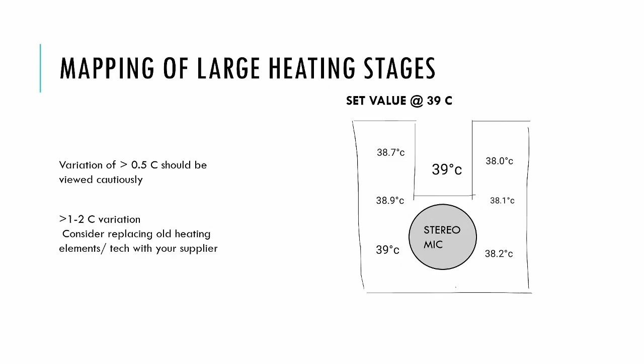When you're calibrating large heating stages like the laminar flow heating, it's quite a large area. That's what I have shown in the picture. You have the stereo zoom microscope, and the right hand side and the left hand side. Ideally you should have three separate temperature sensors: for the stereo zoom microscope, that is the heating plate, and the right hand side and the left hand side. Some manufacturers just have one sensor, and the problem is there is a large temperature variation happening across the table. If the variation is around 0.5, it is okay, it is normal. If it is more than 1 or 2 degrees, then there could be cold zones and hot zones. Only if you map it when you're doing the calibration can you detect all these things.